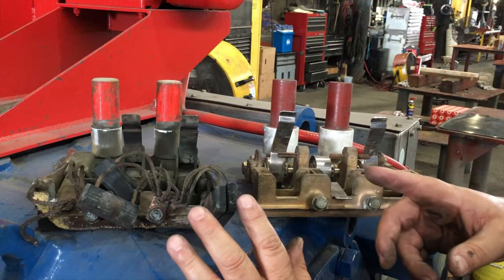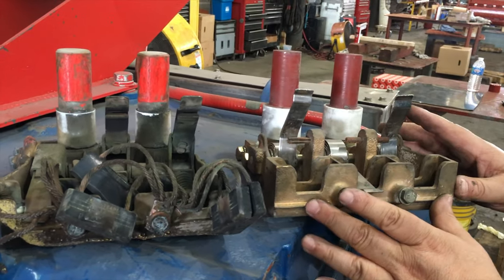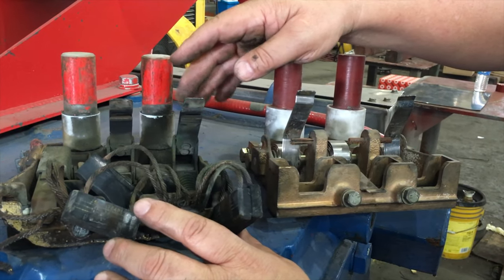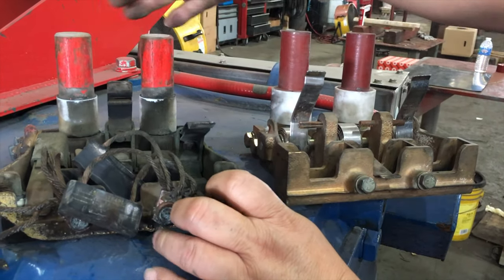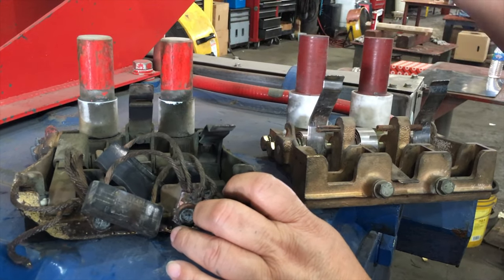Here at Global Tech, we promote the constant tension brush holders. This is a constant tension brush holder; this is not a constant tension brush holder. These tend to seize over time and they'll freeze up — I just shifted it and it's stuck.